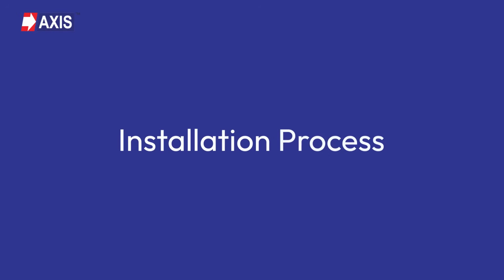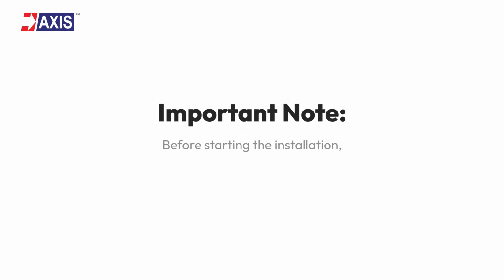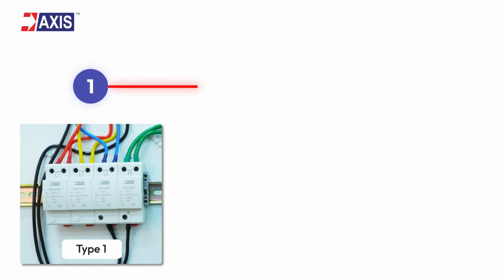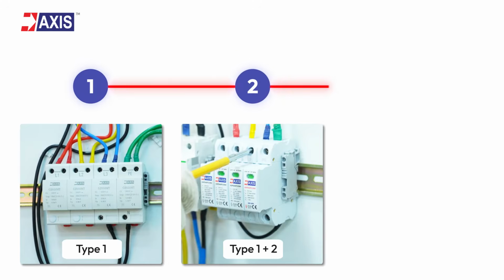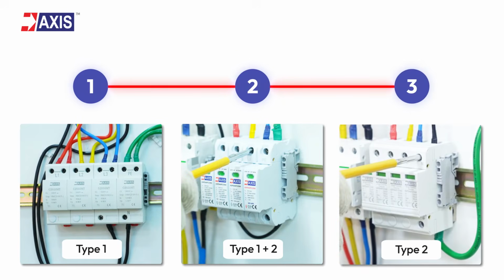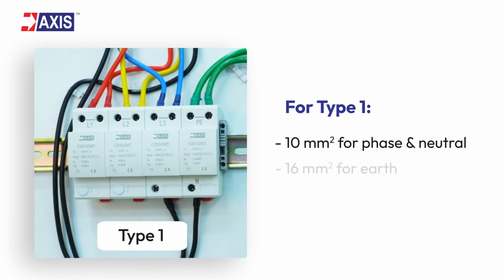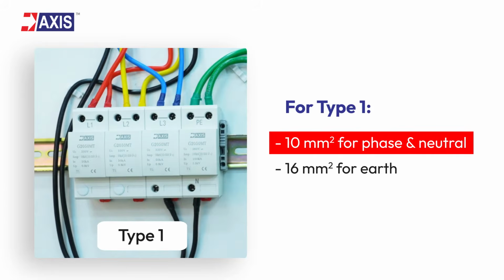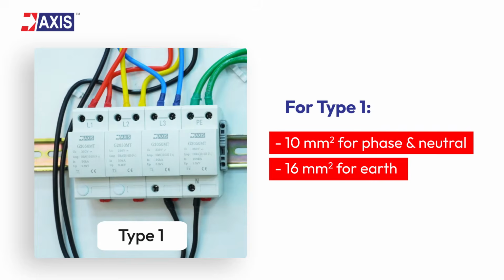Finally, let's start with the installation. An important note: before starting the installation, make sure to switch off the power supply. First, we will install a Type 1 SPD, followed by Type 1 plus 2 and Type 2 SPDs. The installation procedure is the same for all. For Type 1, we will use a cable size of 10 square mm for phase wires and neutral wire, and 16 square mm for earth wire.